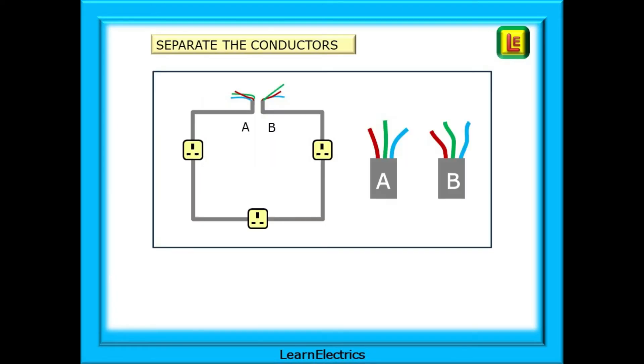At the consumer unit, we must separate the six conductors that make up the ring circuit. If it's twin and earth cable, we'll have an A cable and a B cable. If they are singles, we must find which three wires belong to one set, the A's, and which three to the other set, the B's. I then fasten them together as separate sets with a cable tie.